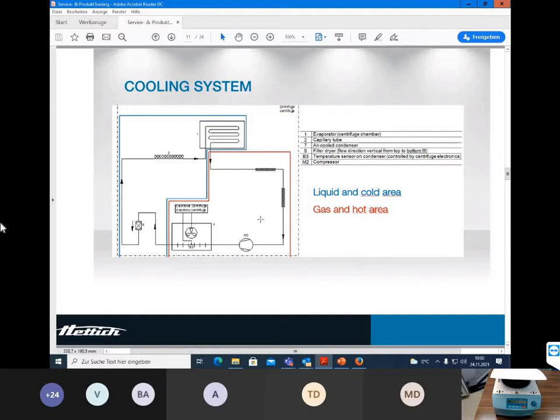liquid. The cooling is in gas. This is a hot area. It's not a liquid, it's a gas. The gas goes to the condenser. The fan of the condenser cools the gas, and then it flows here in a liquid, flows here to the dryer, to the capillary tube, and then to the chamber. This is the chamber of the centrifuge. In the chamber, it's cooled, and then goes back to the compressor.